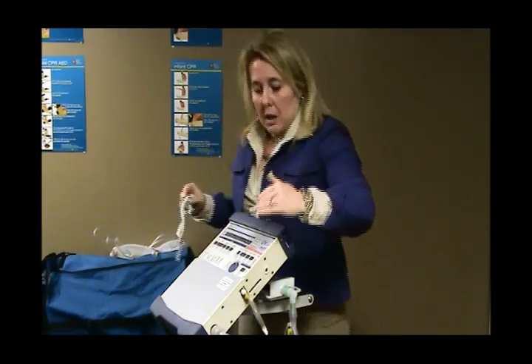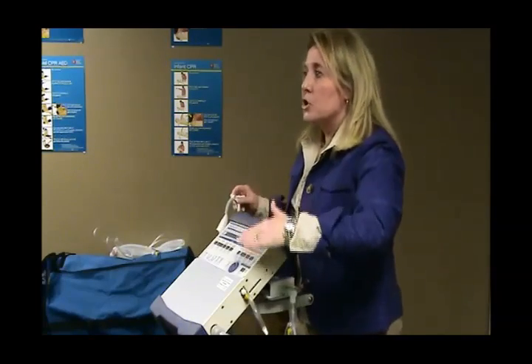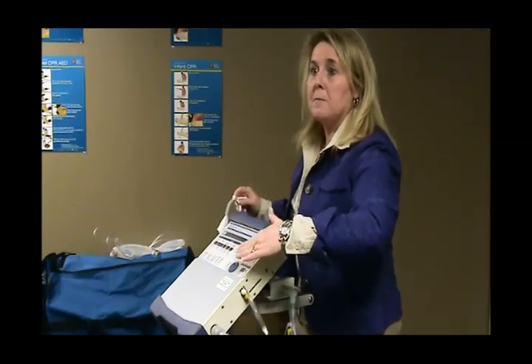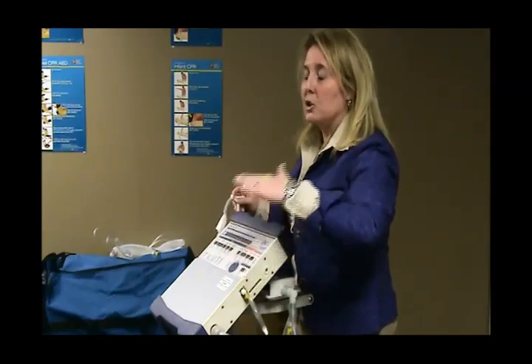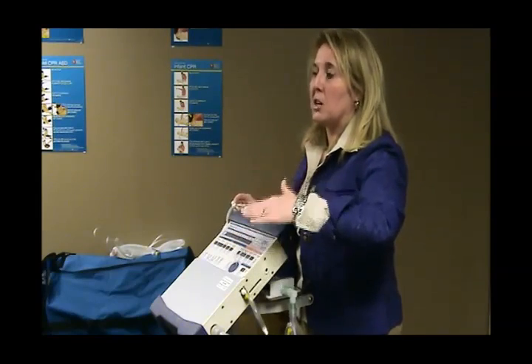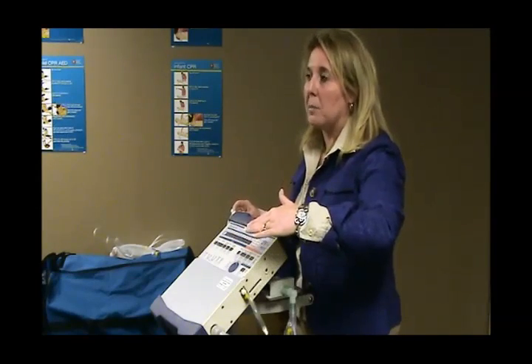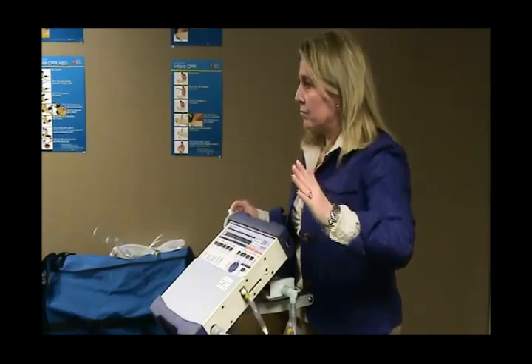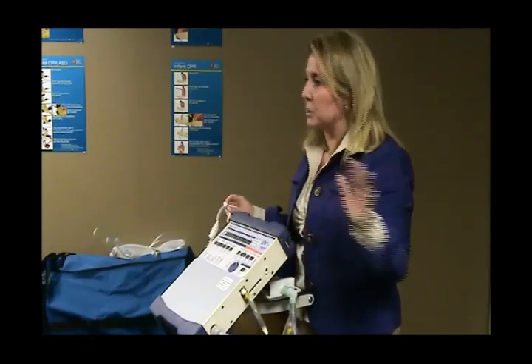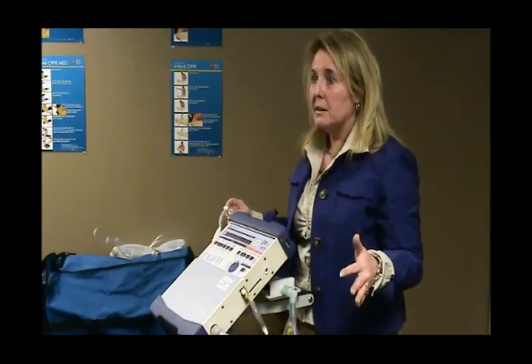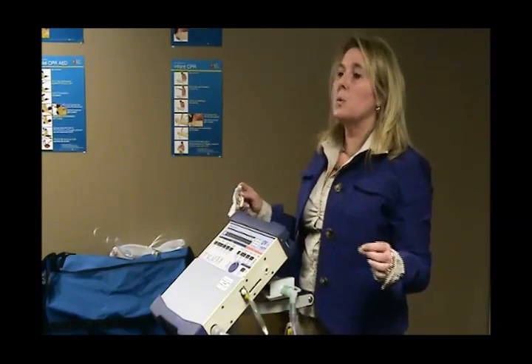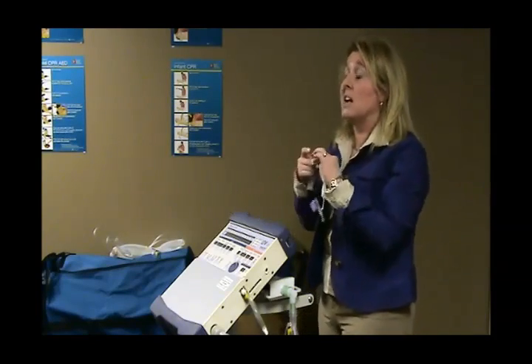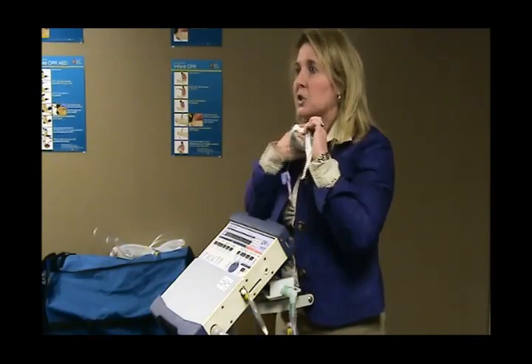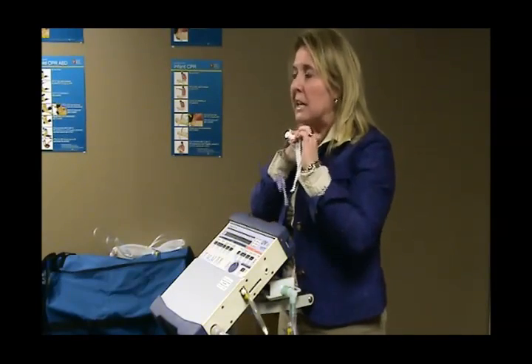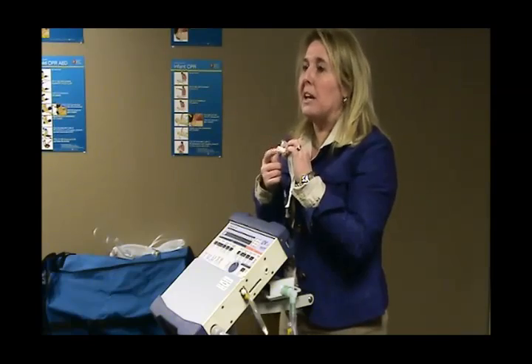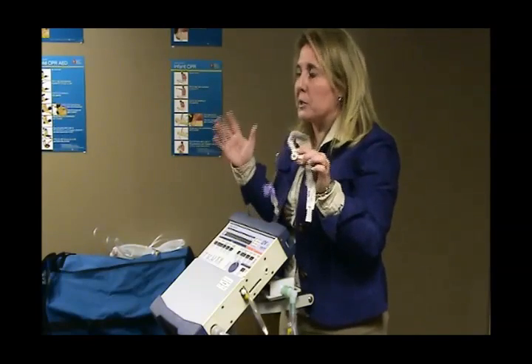So, minute ventilation alarm should always be on at least 0.1, never less than that. Do not let anybody, or let your nurses, be talked into shutting off the low minute volume alarm, especially on pressure ventilated patients, just because. You need an order for that, okay? There are very rare situations where a patient still has a tracheostomy tube because we're waiting to have surgery to fix something in their trachea, and they don't really need the tube to breathe, but it's holding their airway open for some strange reason.